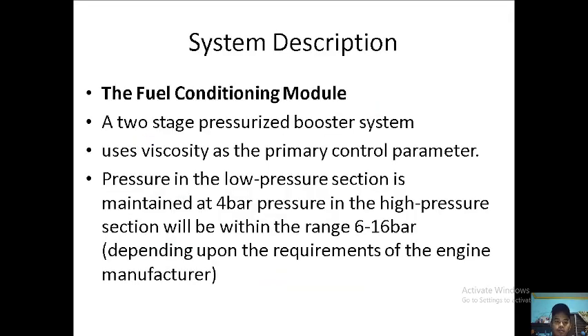Okay, so the fuel conditioning module is a 2-stage pressurized booster system. It has a low pressure and a higher pressure stage. It uses viscosity as the primary control parameter. We are using the viscosity requirement based on the manufacturer's recommendation. Pressure in the low pressure section is maintained at 4 bar, while in the high pressure section we will be maintaining a pressure of 6 to 16 bar, depending upon the requirements of the engine manufacturer.